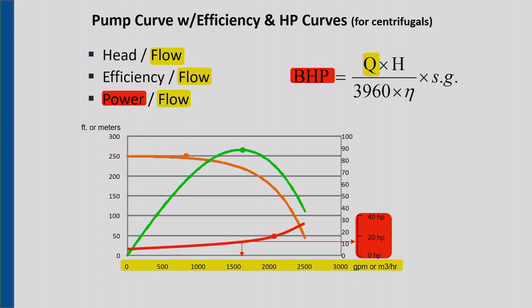Looks at that, wait a minute. I just closed the discharge valve. That pump's really working hard now. How come my current went down? Because when you closed the valve, the flow went down. Okay? So this is true for centrifugal pumps. It tends not to be true for axial flow pumps. They look more like a boat propeller than like a centrifugal impeller. It tends to be the other way.